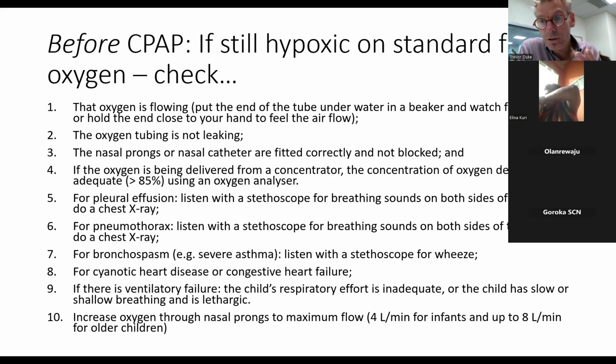You should also, if you're giving oxygen through a concentrator, check that the concentration of oxygen being delivered is adequate, and you can use an oxygen analyzer to do that. I'll show you one of them towards the end. You should check some things about the patient.